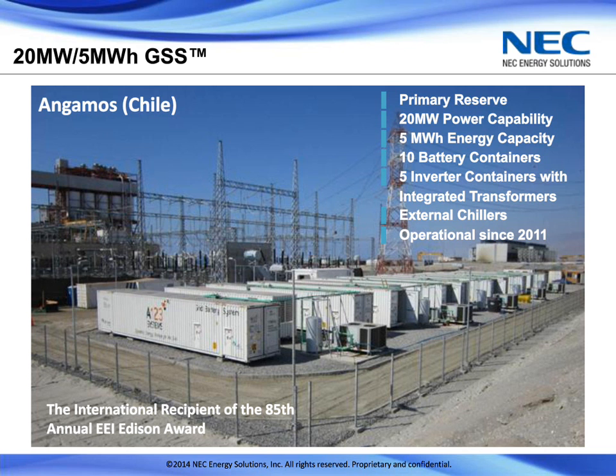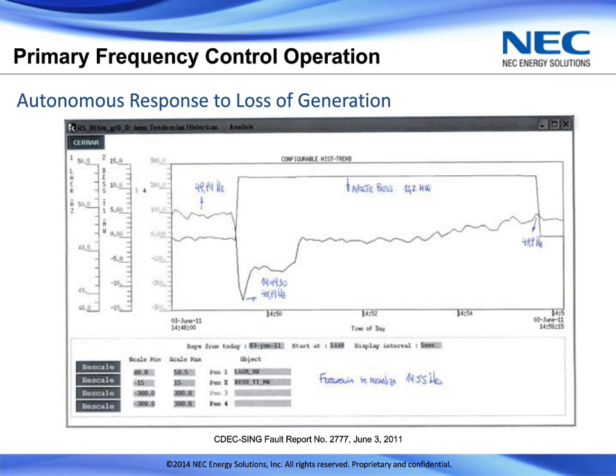So how are they doing in operation? I've pulled 2 charts from a little while ago that show the response of the GSS to a frequency disturbance. In this case, this chart is pulled directly from a CDEC-SING fault report from June 3rd, 2011. And it shows the autonomous response of the GSS to a loss of generation. If you look at the chart, the blue line represents the frequency, which is normally at 50 hertz in the beginning. Now, shortly into the chart, you see a disturbance where you've got loss of generation, and of course the frequency then drops precipitously.